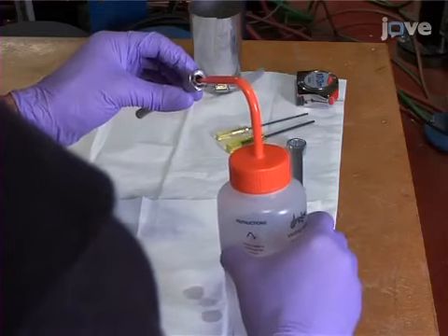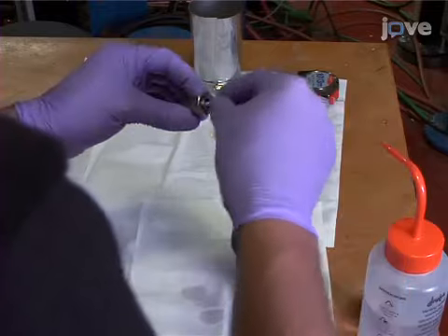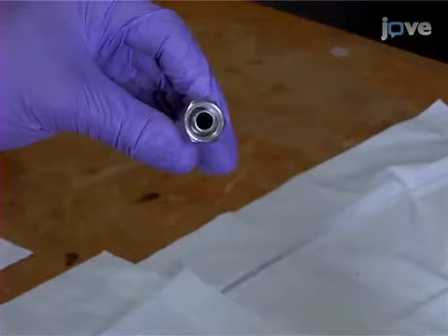For cleaning, fill the tube with approximately 1 milliliter of ethanol and scrub the inside using cotton tips. Then, dry the tube with compressed air.